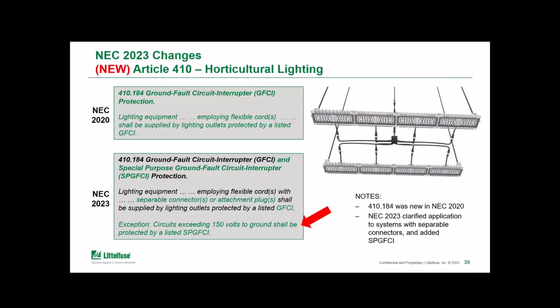One application that was modified in the 2023 NEC codebook is for horticultural lighting, and that's in Article 410. As the demand for these facilities has continued to grow, and yes, that is pun intended, there are larger and more lighting systems being installed. These greenhouse applications can be a challenging environment because it is very wet. They may have automated irrigation systems to keep plants constantly watered and very high humidity.